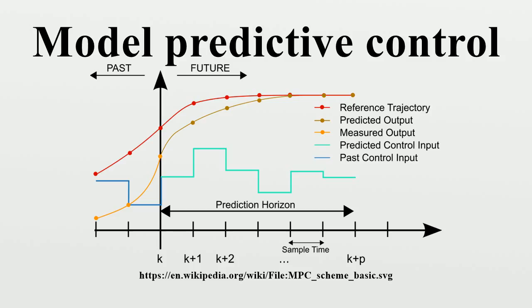When linear models are not sufficiently accurate to represent the real process non-linearities, several approaches can be used. In some cases, the process variables can be transformed before and/or after the linear MPC model to reduce the non-linearity. The process can be controlled with non-linear MPC that uses a non-linear model directly in the control application.